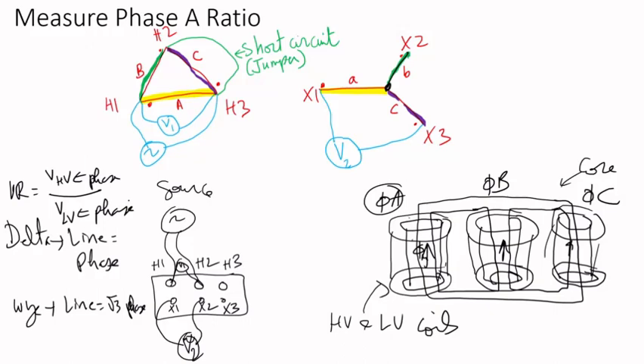But since it's a Y, I can't access the neutral, because it's not brought out. So I can only measure line to line. That means there will be a root 3 factor. So one way you can measure the voltage ratio or turns ratio is by this method. I already talked about one method, so this is the second method.